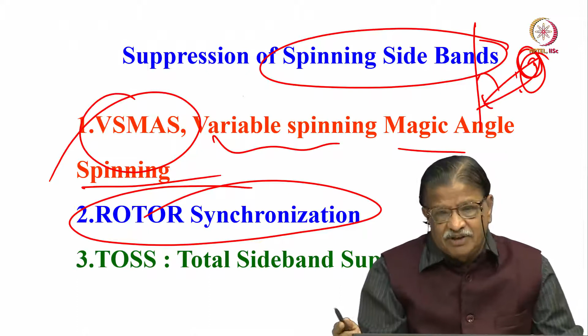And also we have rotor synchronization. I can synchronize the rotor in such a way that spinning sidebands can be eliminated. The rotor keeps on rotating, and I acquire the signal exactly after one rotation. In between it can have the powder pattern; in half a rotation it will come like that, and the next half rotation it will get averaged out. So after one full rotation I acquire the signal, wait for one more rotation, and acquire the signal. I can synchronize the data acquisition with respect to the rotor speed. This is called rotor synchronization, and it can also remove spinning sidebands.